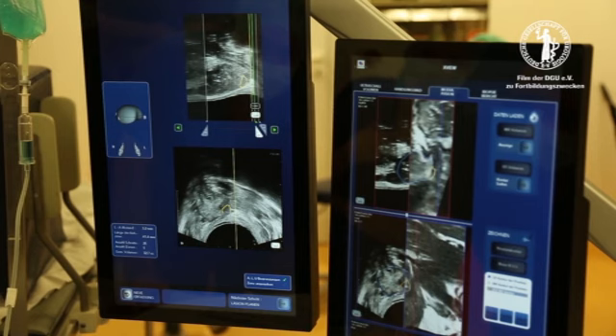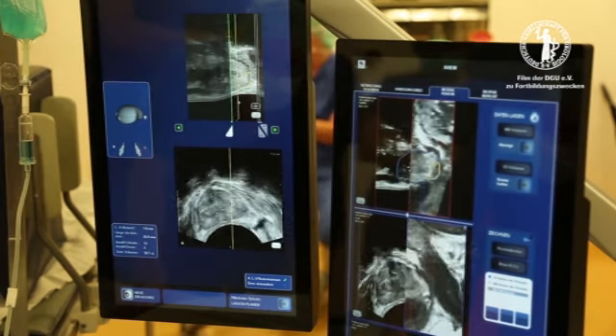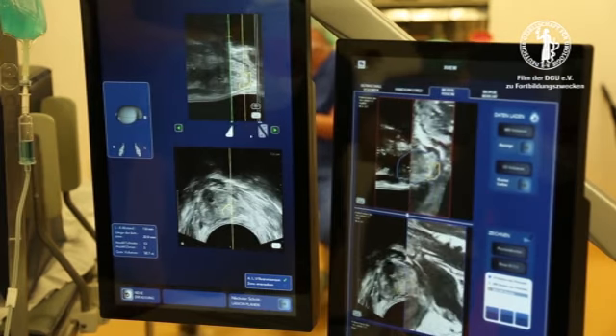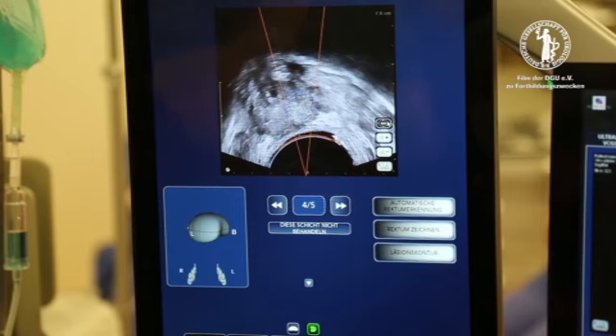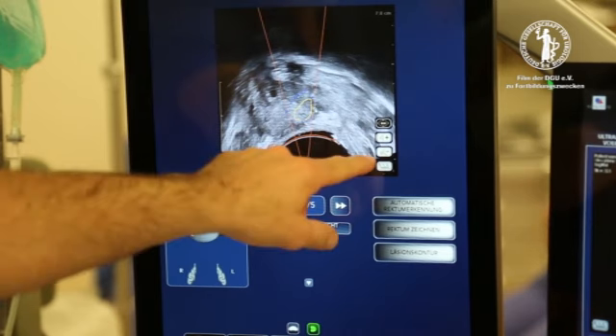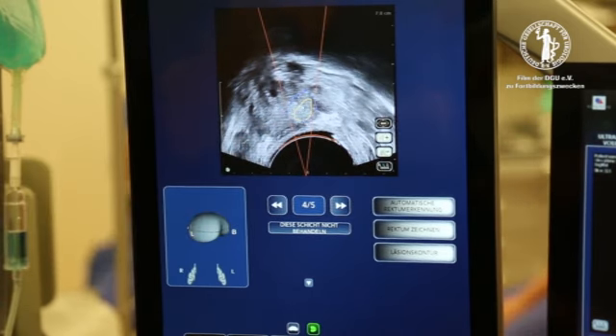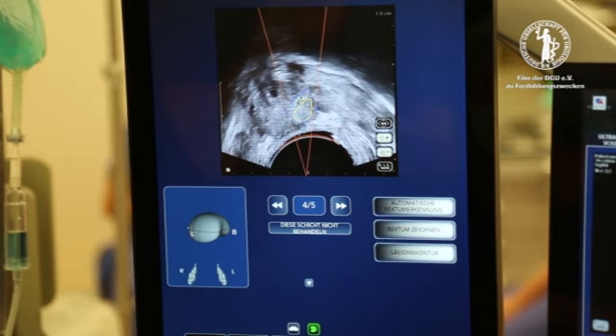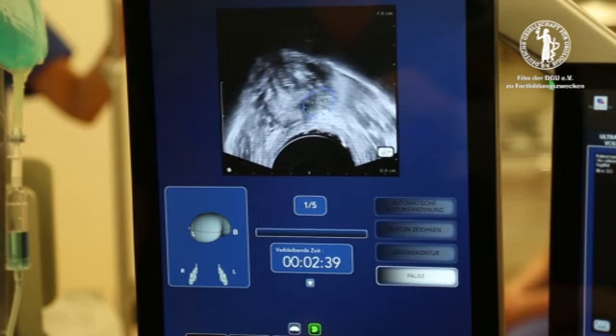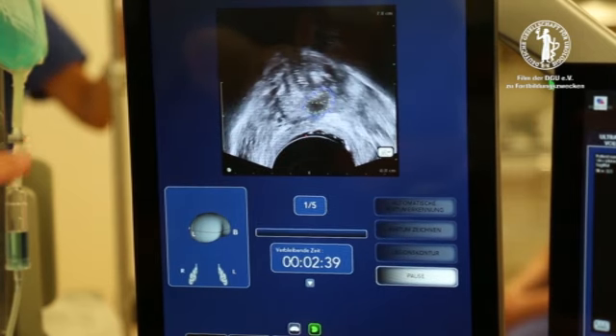The safety distances around the lesion are measured. In the treatment module, the safety margin can be displayed in detail. The rectal wall is automatically detected, and the minimum distance to the first treatment point is 3 mm. The blue contour of the treatment area is drawn by the user, and the orange lines limit the firing zone. The treatment starts at the most anterior point set by the user and progresses in a posterior direction. The probe automatically covers the whole area. The turquoise blue points are automatically set by the software.